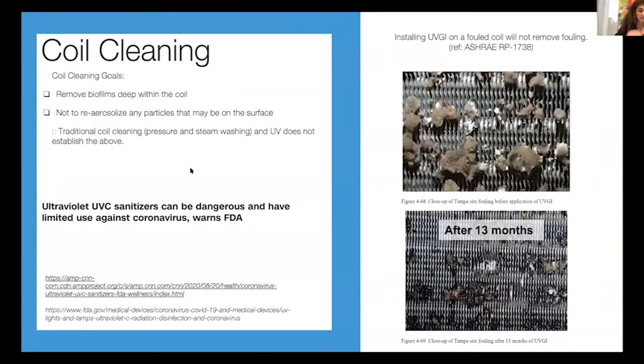And the objective when you choose coil cleaning is to make sure that you are cleaning deep throughout the entire depth of the coils, and you're not re-aerosolizing any particle that's stuck in the airstream. This is specifically important in COVID-19. And also, I know that there is a surge in sales of UVGI. I put here a link for you that explains what the considerations are when you are specking UV. And this is an example from an ASHRAE-funded study. I also put the link.